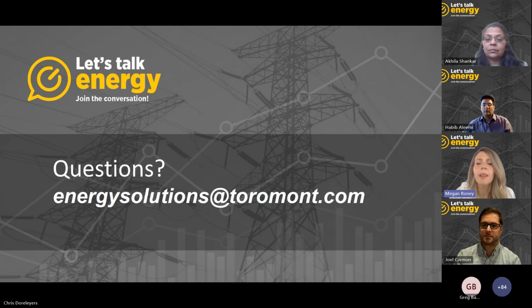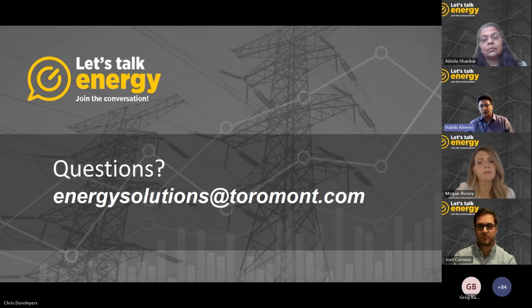Okay, thanks, Joel. Next, oh, go ahead. Sorry, if I could add to Joel's comment, one of the conditions or aspects that we size battery bank systems by is how long the customer needs the battery bank system for. As Joel mentioned, is it 10 years, 15 years, 20 years. And also we can calculate the derating of the batteries, for example, after 10 years, it will reduce its capacity by X percent. And then we can add a module to it to bring it back to the original capacity.